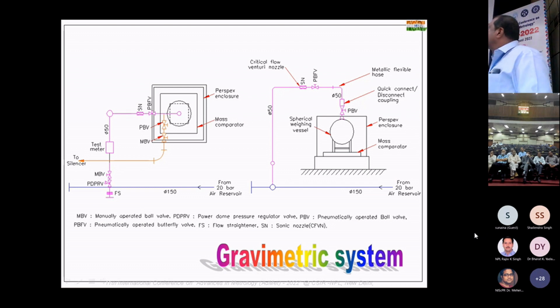this will not work in a calibration method because it's a closed container. When we put air into the container, that generates a back pressure. When the back pressure arises, the flow rate gradually decreases, so we will not get a steady flow rate at the reception. In that case, we will not be able to calibrate the meter because the flow will be unsteady, and the flow will cease when the inlet pressure and the tank pressure reach the same value. So to overcome this issue, we need a steady flow rate.